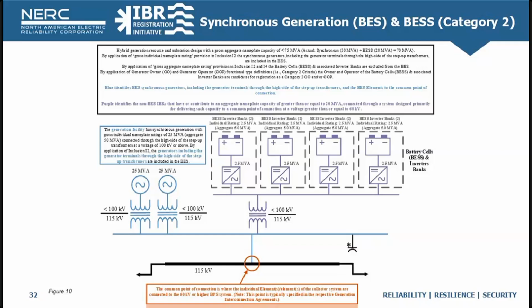The first step in evaluating the resources is to apply the BES definition to the facilities. So by application of the BES definition inclusion I2, the 25 MVA synchronous generators with a connection at a voltage of 115 kV are included in the bulk electric system. Further application of the BES definition provisions by application of the aggregate nameplate capacity provision of greater than 75 MVA that's included in inclusion I2 and I4, the 20 MVA battery energy storage component is excluded from the BES because the total facility aggregate nameplate rating is 70 MVA, which is below that 75 MVA threshold.